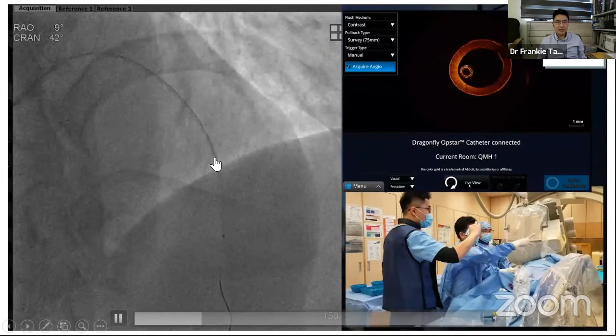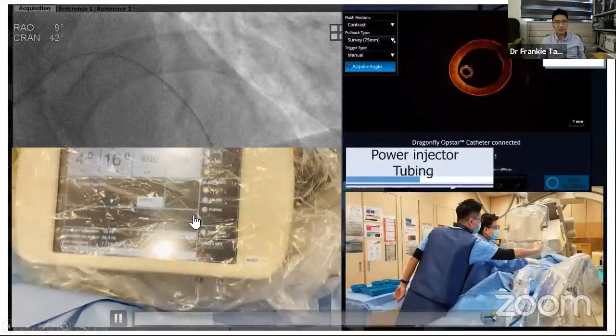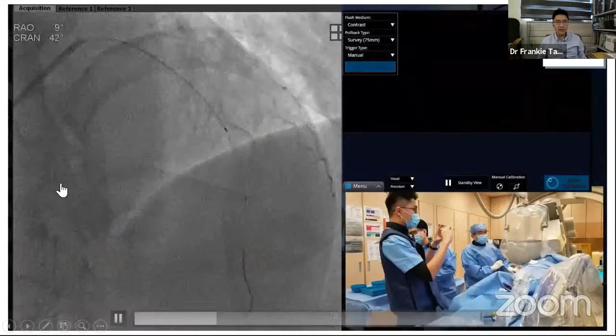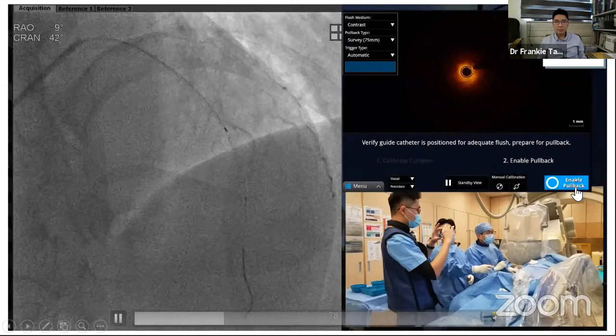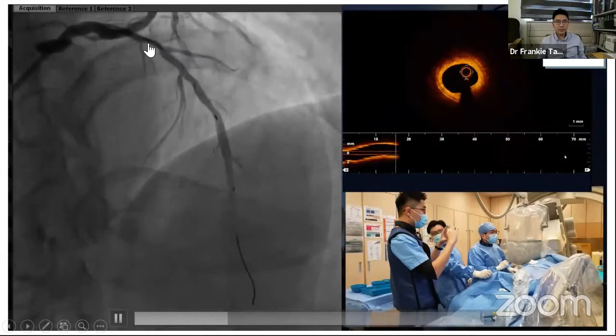So we park the image sensor distal to the lesion, and then we all know that OCT needs contrast. Sometimes we can use the injector, like in our lab, we like to use the injector. Some people like to use the usual syringe. So this is a connection tubing. We try to make the tubing not too long because we really want to flush better. So we adjust the contrast volume, the flow, and the PSI. So we make sure we have a very good guiding. Make sure that our image is distal to the lesion of interest, and then we click the enable button, and then we inject contrast. And this is automatic pullback mode, so the OCT will activate by itself.